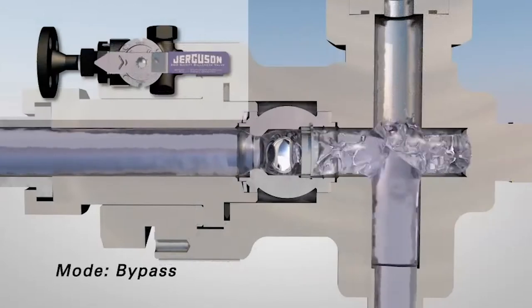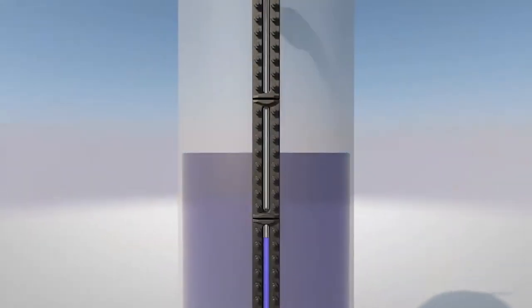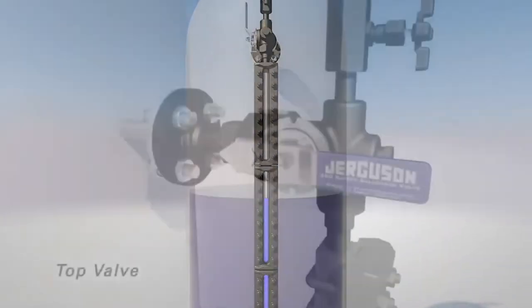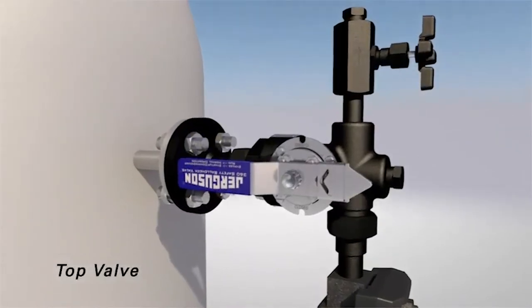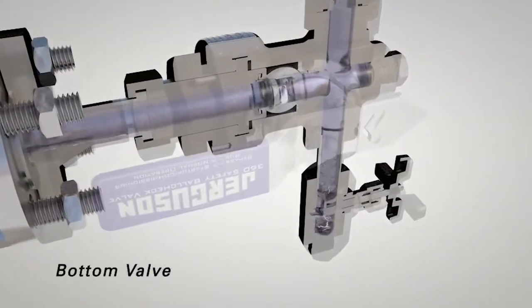Fluid will now flow through the valve and into the glass gauge without seating the ball check. Once the level stops rising, move the top valve to the run position, then the bottom valve. The valve is now ready for normal operation.